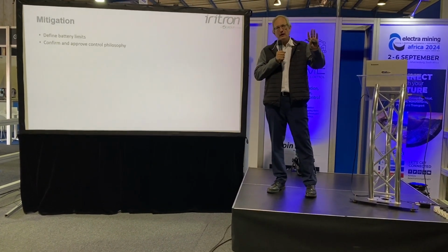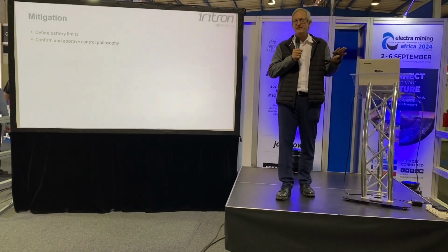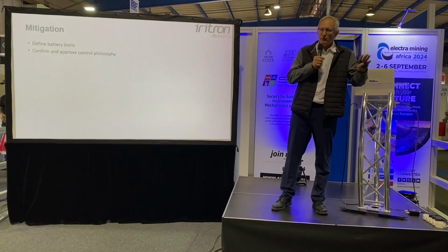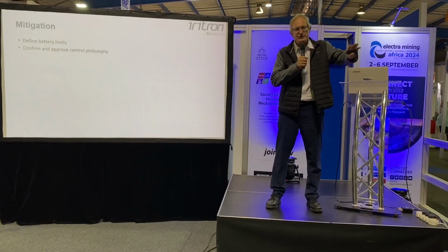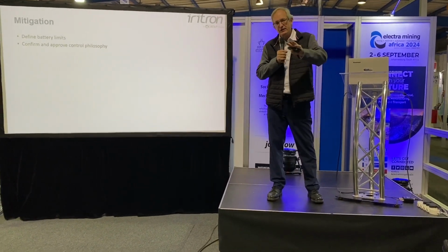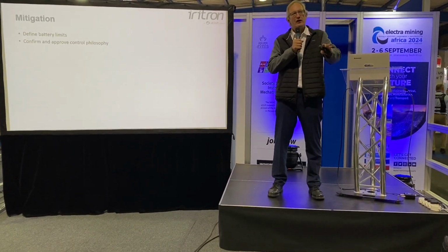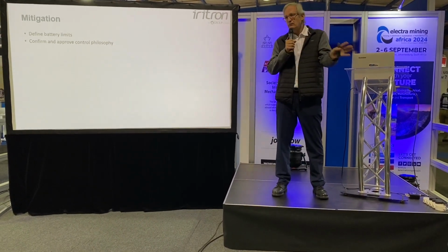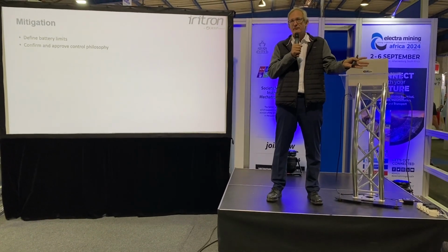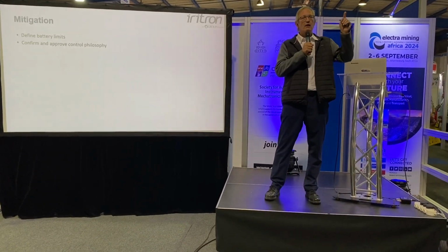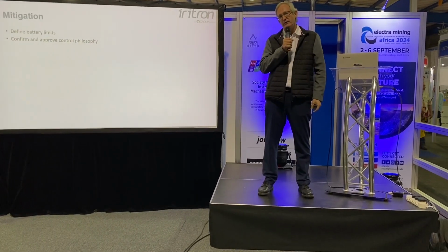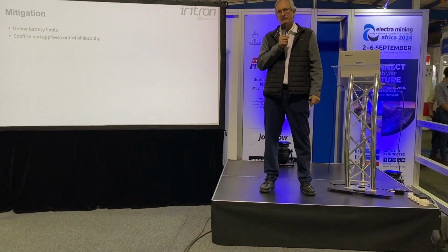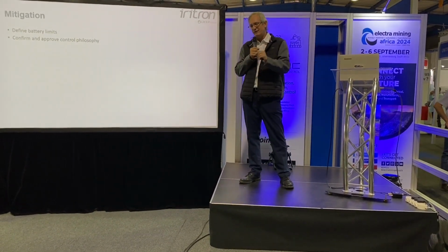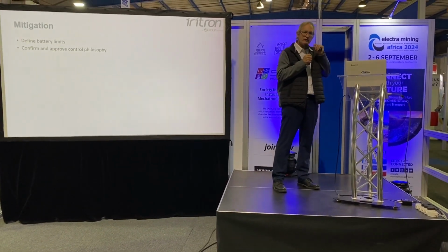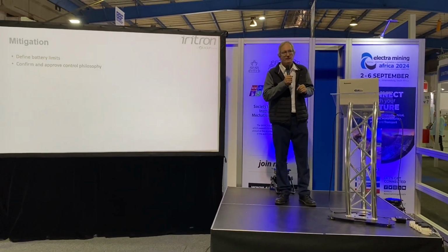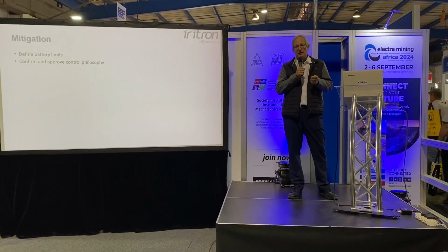You have to have an approved control philosophy. When they tell you that the code is in the PLC and the visualization is in the SCADA, and that will show you how the plant is controlled, don't accept that. Because even if you do that, you can rewrite line for line, and they will still tell you that the plant doesn't operate like this. You have to make changes. So get the control philosophy defined up front so that you're sure that you have the correct control philosophy. That will save you nights and nights of pain.